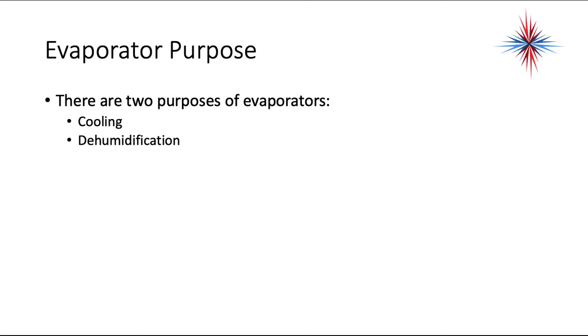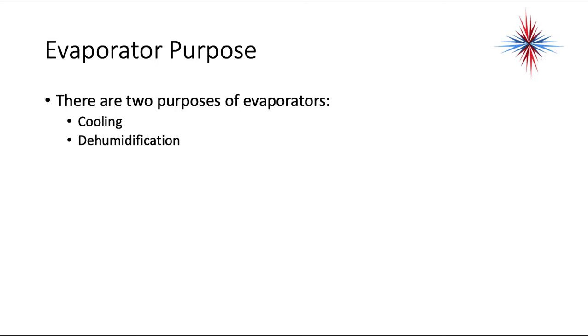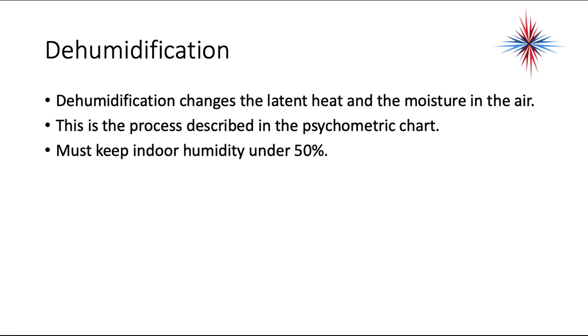Evaporators both cool and dehumidify — something a lot of people don't realize. Cooling changes the sensible heat content of the air, which you can actually measure. Dehumidification changes the latent heat content and the moisture in the air — the process described in the psychrometric chart. We must keep indoor humidity under 50%. When humidity in the air space is lower, people feel cooler. Our primary purpose of air conditioning is to dehumidify — that's why there's a lot of condensate that comes off AC systems; we pull moisture out of the air, turn it to water, and drain it away.